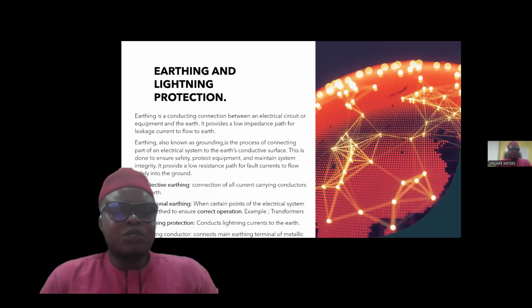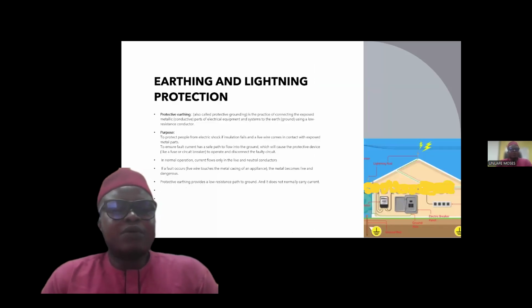There are two ways we do this: protective earthing and functional earthing. Protective earthing is the connection of all current carrying conductors to earth, while functional earthing is when a certain point of an electrical system is earthed to ensure correct operation of equipment. There is a need for us to understand properly what protective earthing is. Protective earthing is the practice of connecting an exposed metallic part of electrical equipment and system to the earth with a low resistance conductor.